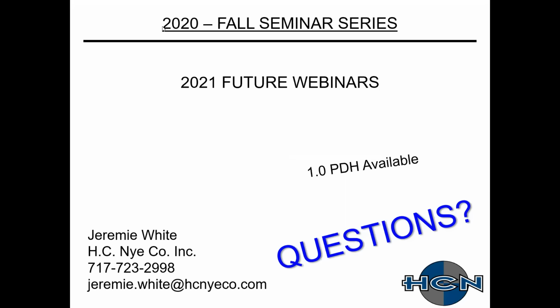I know 90.1 actually calls out, I think, 50% turn down for your exhaust. That's good if you have an unlisted hood. If you're using a listed product, though, it's hard, because you're going to start getting below a certain point, and if you get below that point, you're not in compliance. So when I was at Captive, typically what they did was say 20% turn down, and it's really based on your system. They started implementing a startup service with their guys, and they would go out and base it on what kind of cooking equipment and what kind of stuff you're doing. It was more of a live process, because every job and every application is different. You can't have a cookie cutter, so I can't say this is it. But from a factory standpoint, they were looking at 20 to 30% typically.